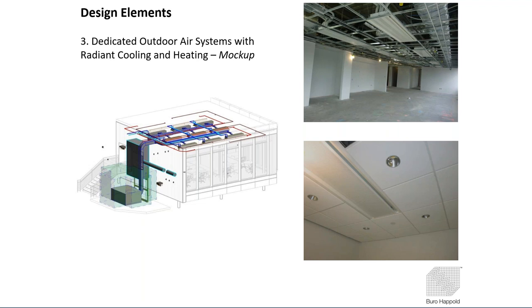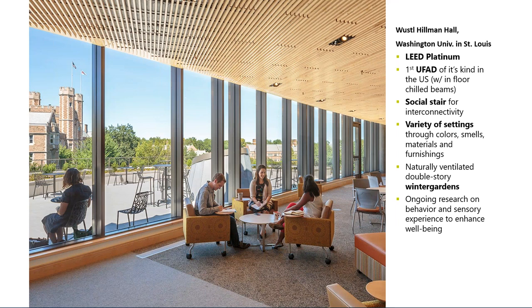And in doing that mock-up, we even tweaked the chill beam in the field and put a manual damper on it to be able to adjust the throw patterns of the chill beam. A lot of times you can do it based on just what you get out of the catalog data, but there are times when mock-ups are necessary, if you're trying to do something new, or if you see something that you're concerned about, but you still think it's best for the project to follow through with that application. So I highly encourage it when you can do it.